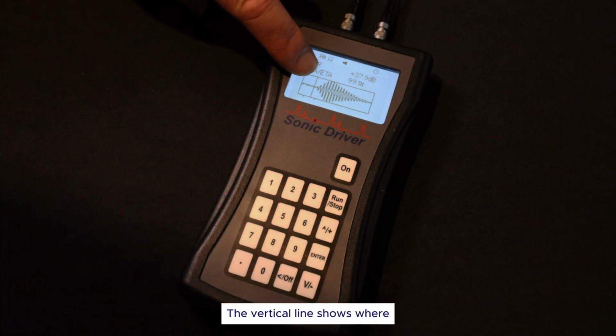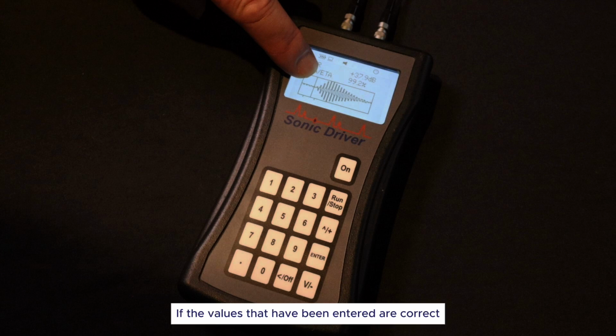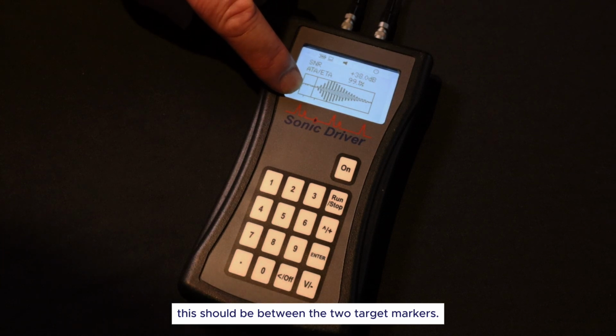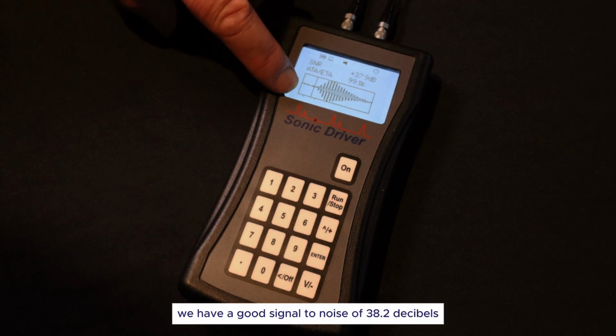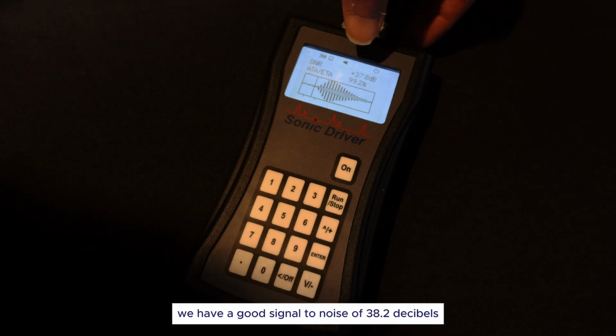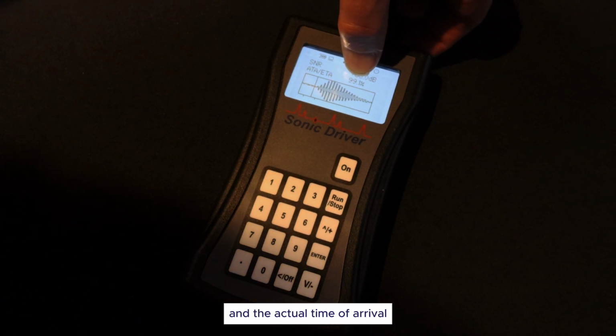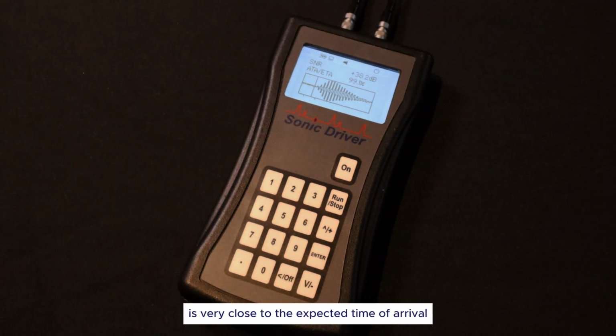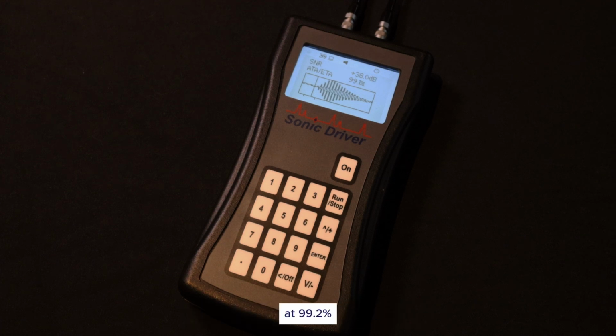The vertical line shows where the flow meter is detecting the ultrasonic signal arrival. If the values that have been entered are correct and the transducers are the correct spacing apart, this should be between the two target markers. In this example, we have a good signal to noise of 38.2 decibels, and the actual time of arrival is very close to the expected time of arrival at 99.2%.